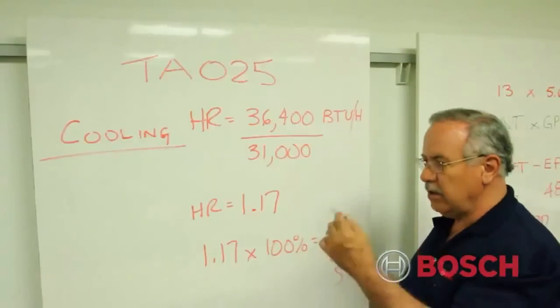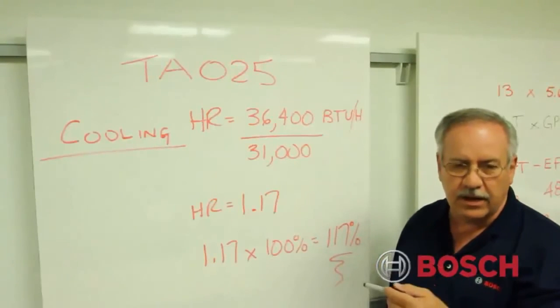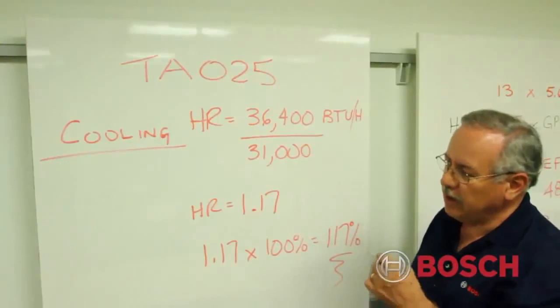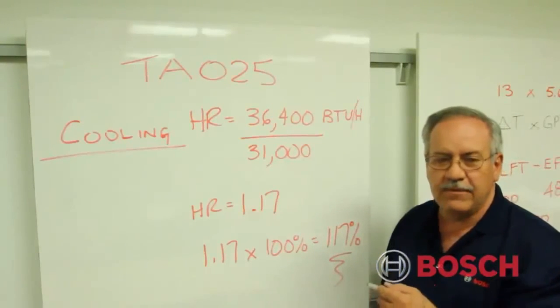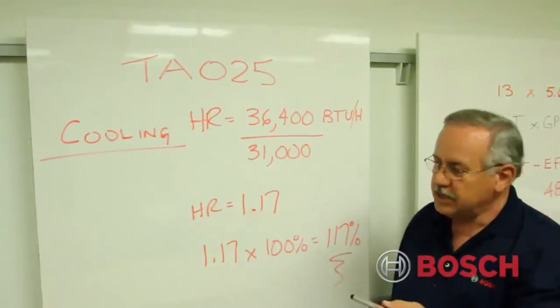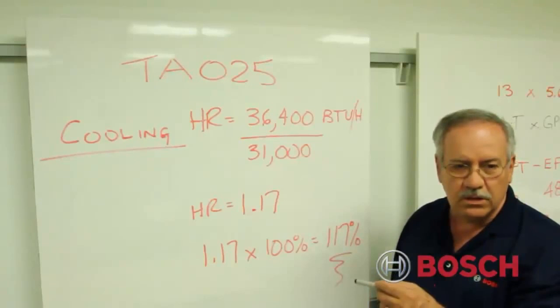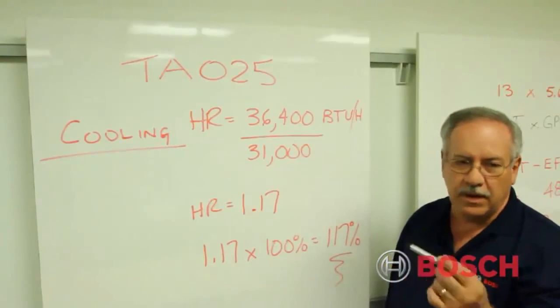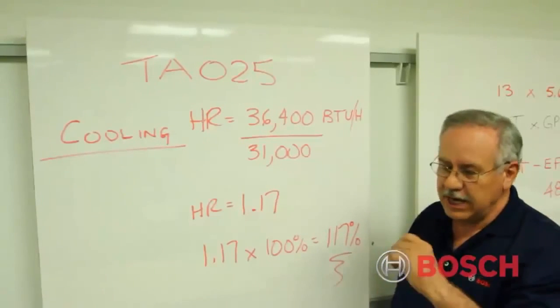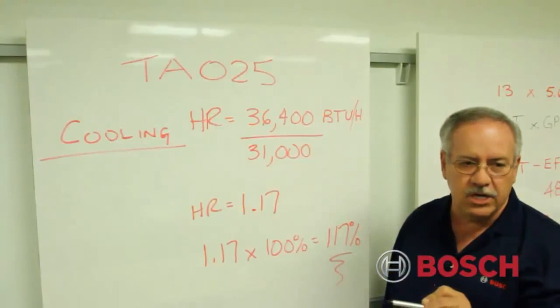Whether we're operating in the cooling or heating cycle, the measurements and the calculations are the same. If we were below 90%, then we would have to think beyond the concept that maybe something is wrong with the water circuit or the air circuit or possibly the refrigerant circuit. The last thing we would want to do is put our gauges on this machine.